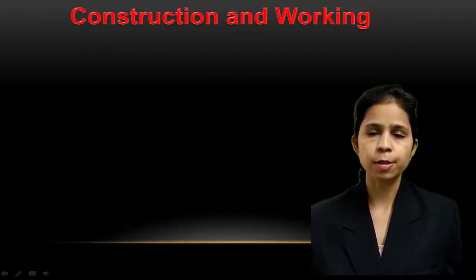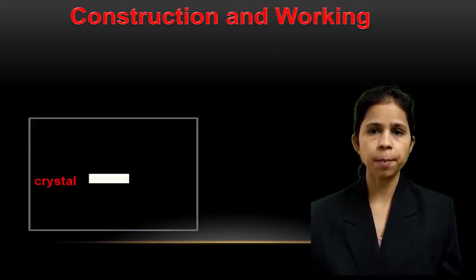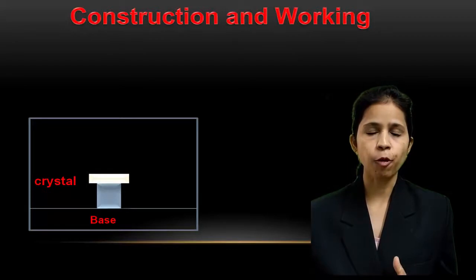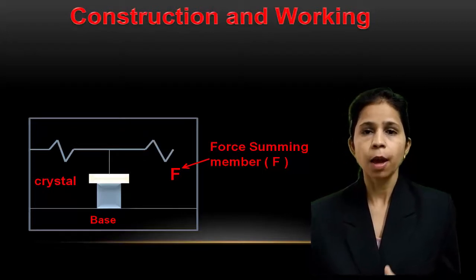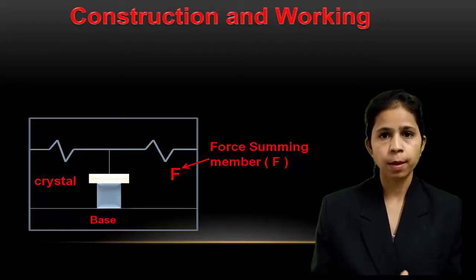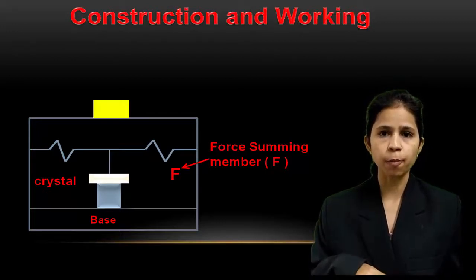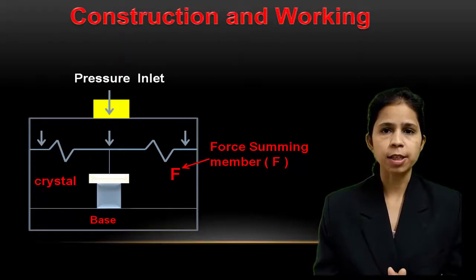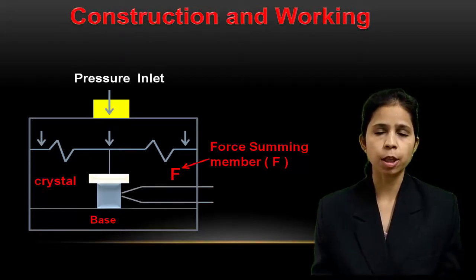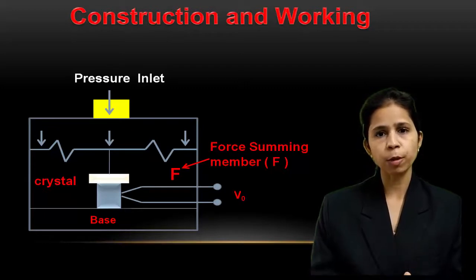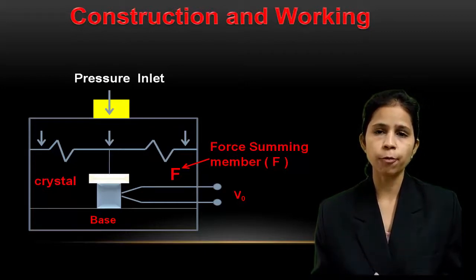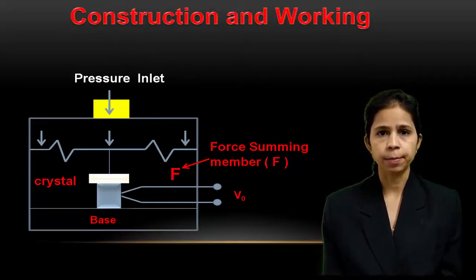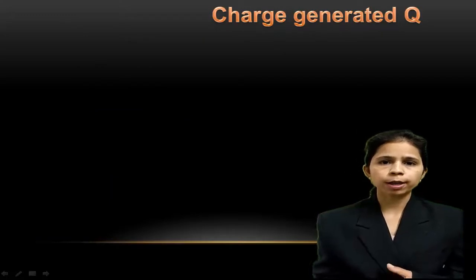The construction of a piezoelectric transducer consists of a crystal kept between a solid base and a force-summing member F. The force-summing member consists of all the mechanical elements used to convert the applied force into displacement. When the pressure on the top surface of the crystal is increased, charges are developed on the opposite faces, so a potential difference is developed — and the magnitude of this potential difference is proportional to the pressure applied. If you decrease or release the pressure, the potential difference is again developed but with opposite polarity. The voltage produced also depends on the orientation of the crystal.